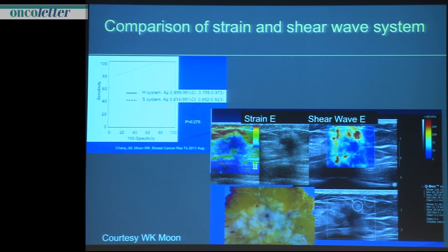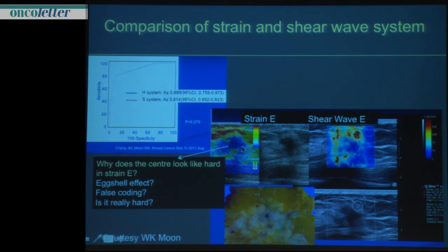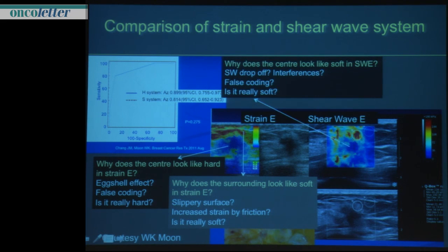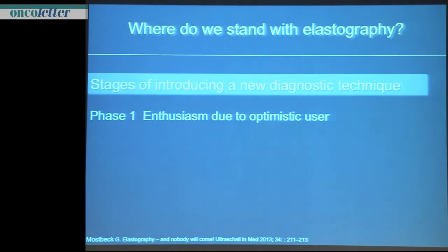This image from Moon, also an EFSUMB lecturer, illustrates problems we still face. In the strain image, the center is hard and the surrounding tissue is soft. But looking at the same lesion with shear wave elastography, the center is soft and the surrounding is stiff. What is the definitive truth? There is a lot of work to do and you have to understand the technological basis for why this can happen. My theory is there are interferences in the center in the supersonic technique.